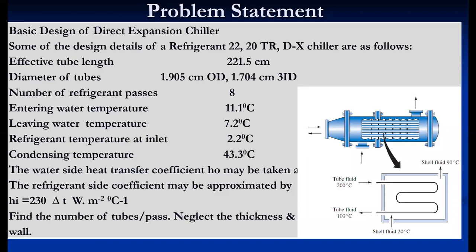This is a DX type shell evaporator where refrigerant flows through the tubes. There are 8 number of passes in one shell. For example, pass one, pass two, pass three, pass four — like that, eight passes total. The refrigerant inlet temperature is 2°C, and refrigerant outlet temperature is also 2°C because we assume pure saturated state. Shell inlet water temperature is 11.1°C and shell outlet water temperature is 7.2°C.